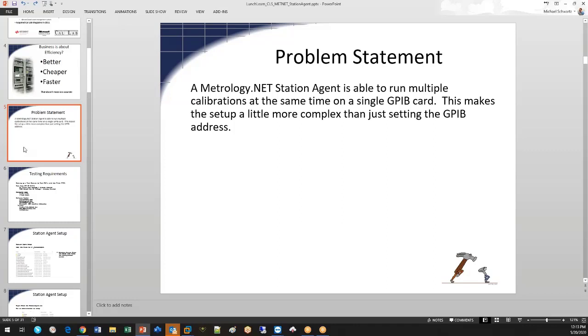And we've run as many as 3 simultaneous calibrations at the same time. We didn't see any decrease in speed running the 3 things as far as running them individually, but we ran out of equipment, so we couldn't test it at 4 and 5 and 6 calibrations to see where things slow down.